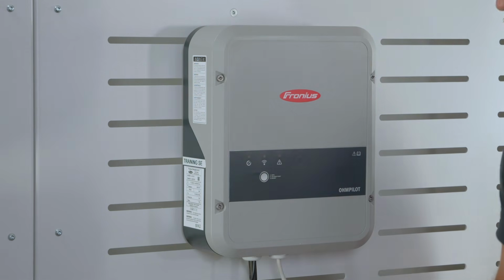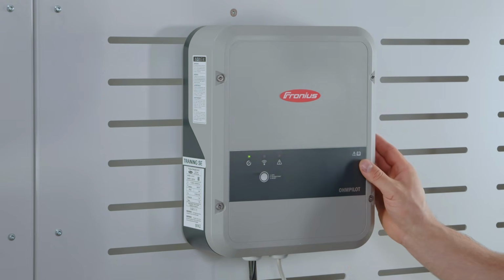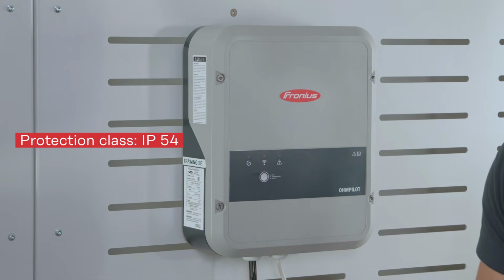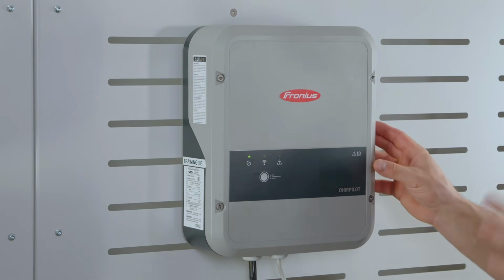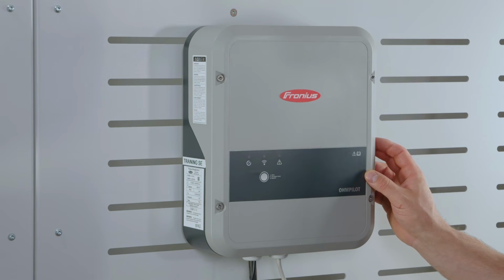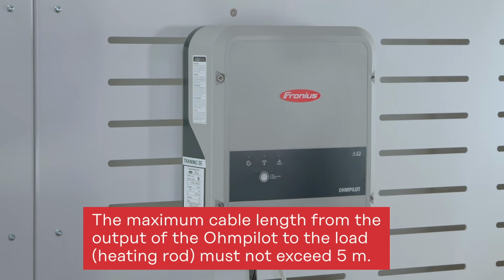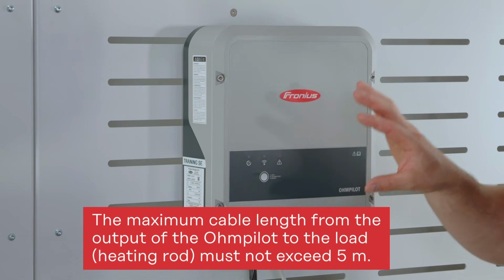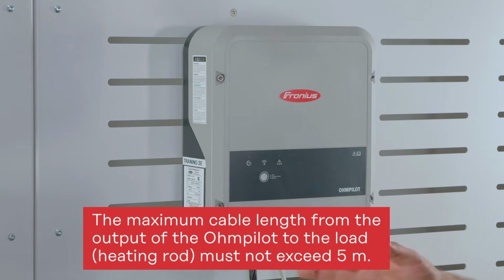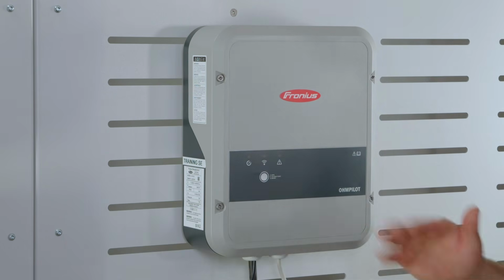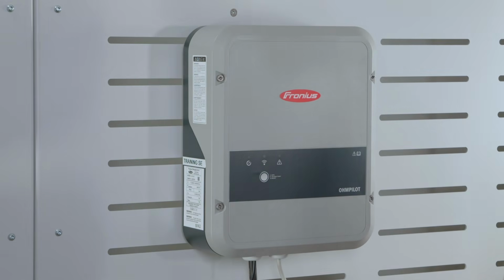All right, we have for the Fronius Ohmpilot not as high an IP protection class as with our Fronius inverters. Therefore, it's very important to remember that this one is placed indoors, direct or in a very close distance to our boiler, which we then might want to use. There is actually also a limitation. Please make sure that the Ohmpilot is sitting no further than 5 meters away of cable distance of the actual heating rod that we want to place finally. So 5 meters maximum from here to heating rod. From here to the inverter, that's not a problem. Our maximum Modbus communication line, if set up correctly, would be 300 meters. So there is no problem there.